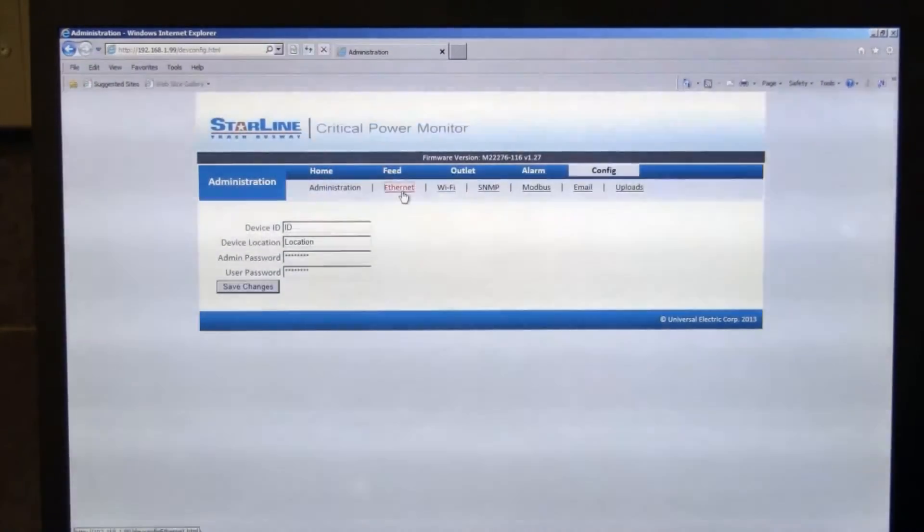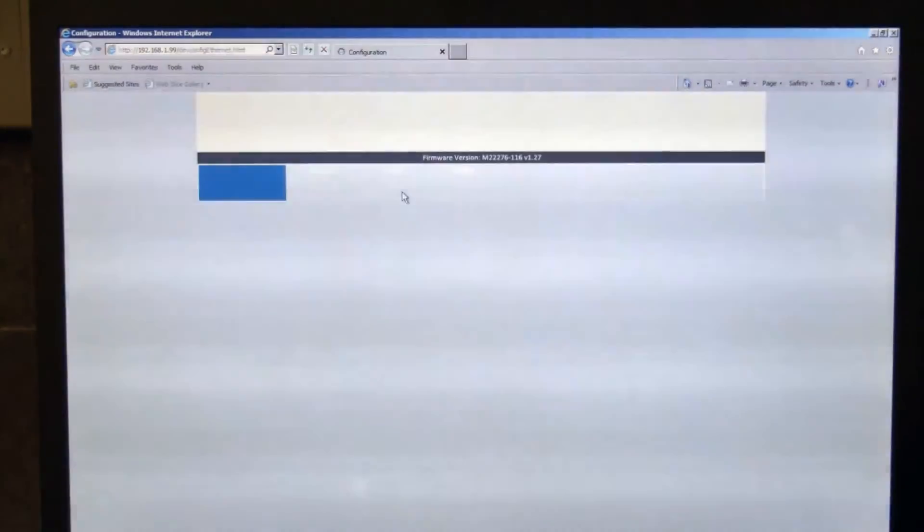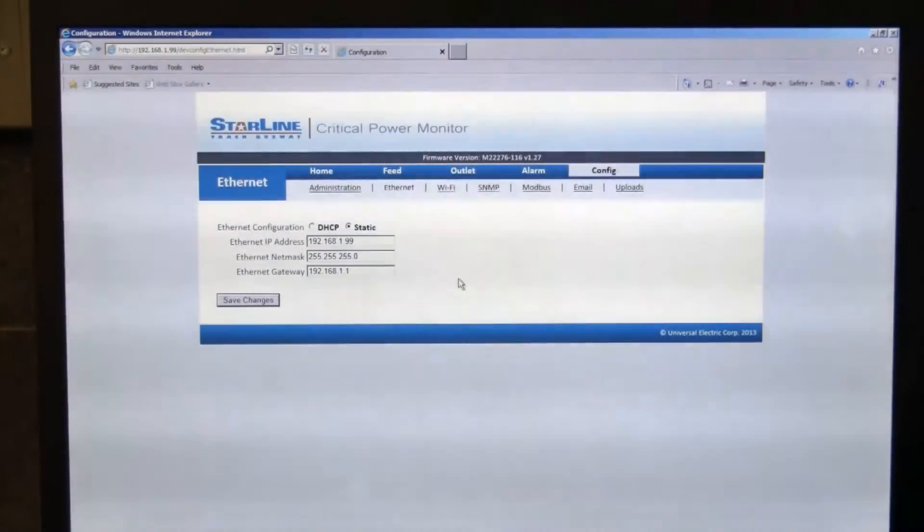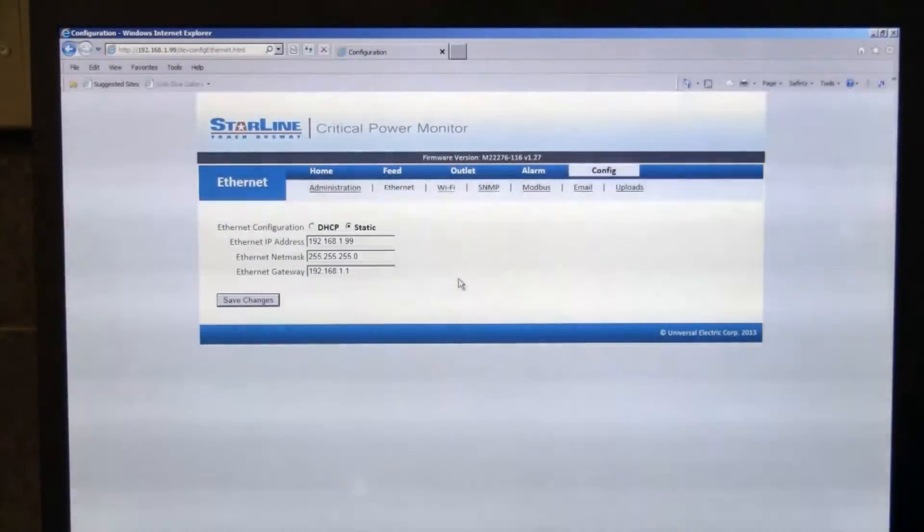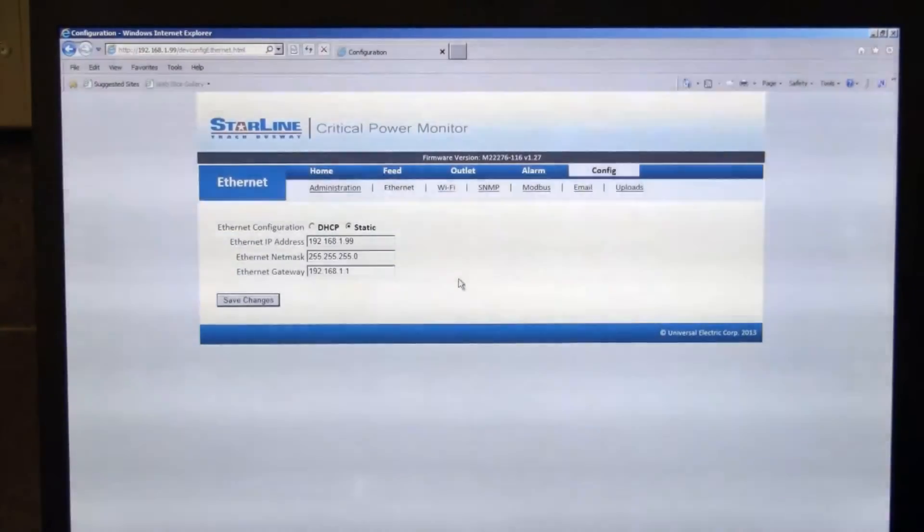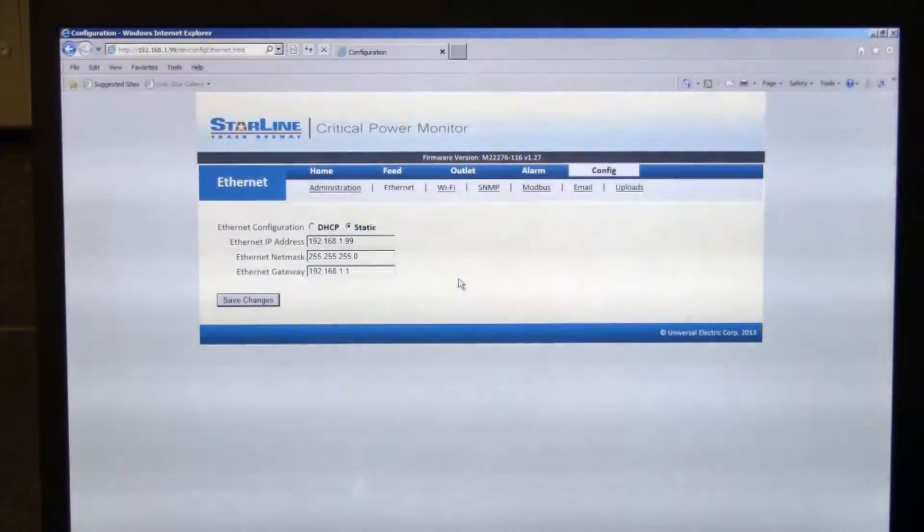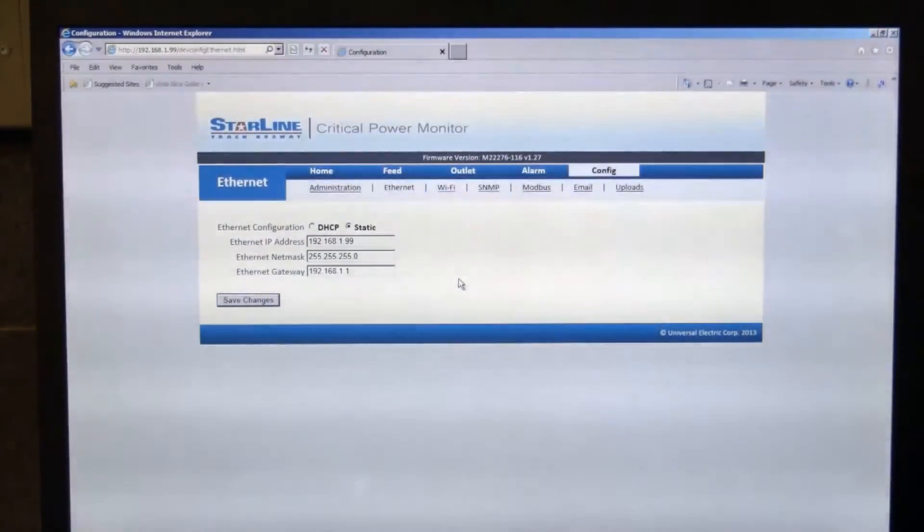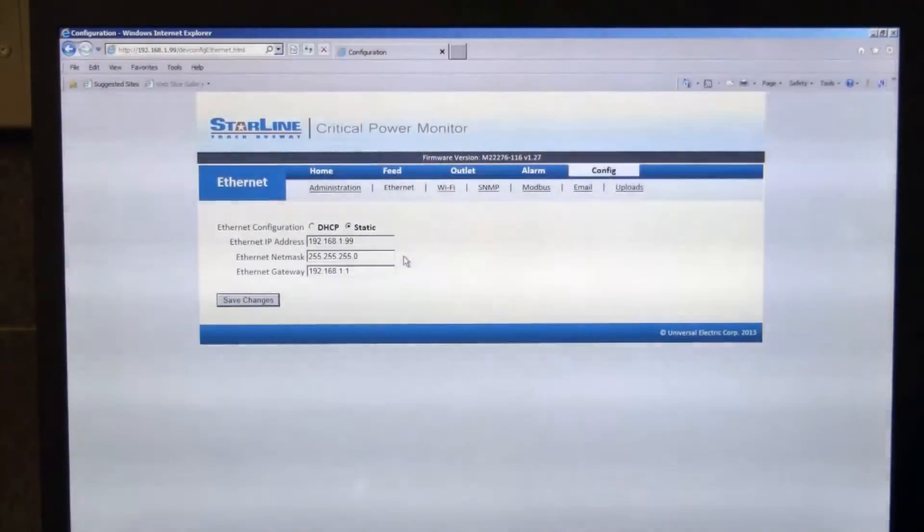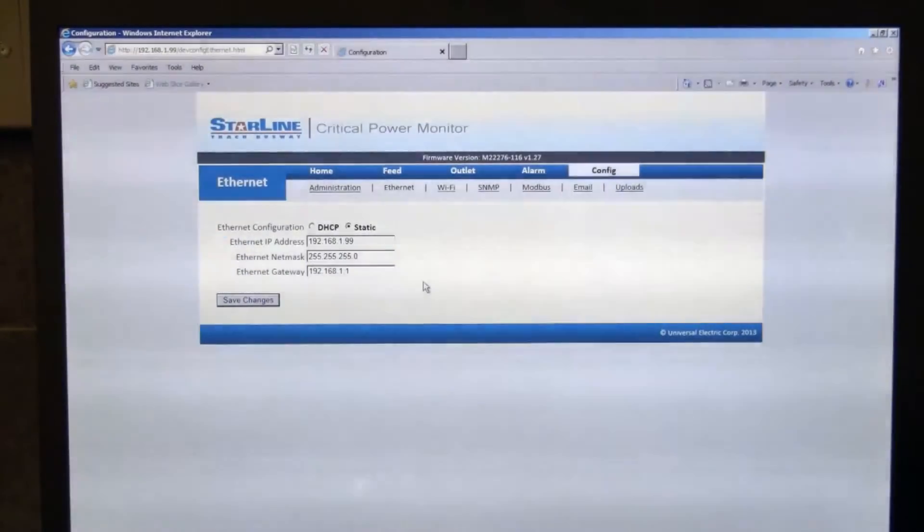Underneath the Ethernet tab, you can set the unit to operate in either DHCP or static IP addressing schemes. You can see there, by default, it is set to static with your IP address set at 192.168.1.99, your subnet mask, and then your gateway as well. So those are all configurable fields. You can also set that to DHCP, and then it will automatically obtain an IP address from your router.